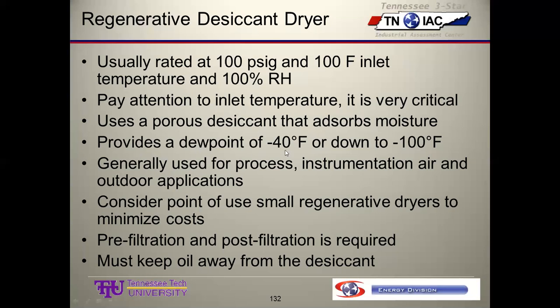So it provides really low dew points. We're saying minus 40 down to maybe minus 100. I'd say our compressed air probably won't see temperatures that cold, so we would not have to worry about condensation if we dry with a desiccant. The problem is they're more expensive to operate. So they're generally used for process, instrumentation, outdoor applications, painting. You want very consistent air, not much moisture at all in the compressed air that is used to spray paint on cars, for example. Lots of specialty applications need these. Or lots of plants where pipes run outside, and in the wintertime, if it gets cold, you're going to get below 32 quite a bit. You can have issues.